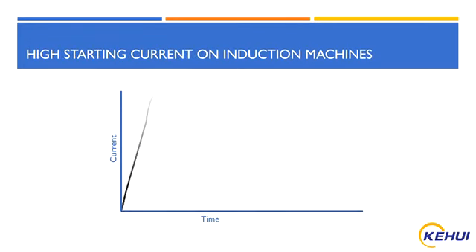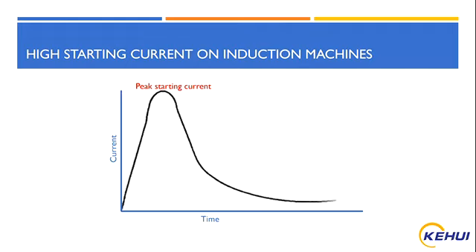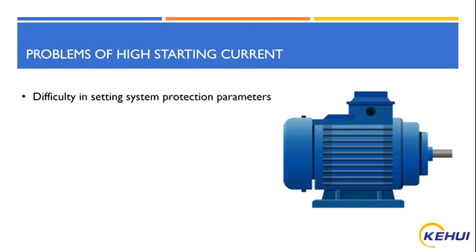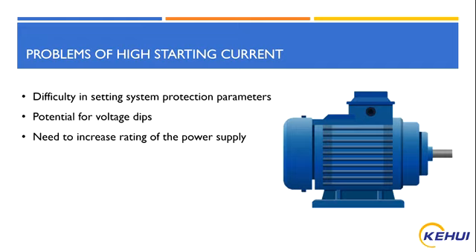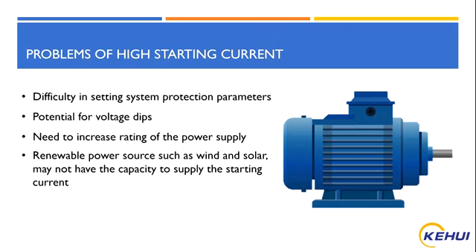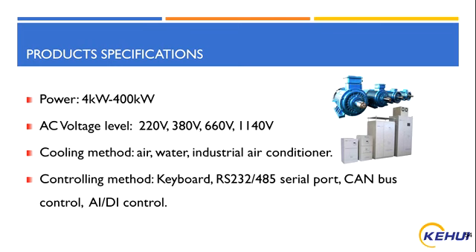A further drawback of induction machines is the very high starting current which they may draw. This will introduce difficulties in making the settings on the protection. It could result in voltage dips on the system and is likely to require an increased rating on the supply, which may not be possible if the machine is driven from a renewable source. None of these issues affects the switched reluctance motor, which can be used for many applications where the induction machine is not suitable.